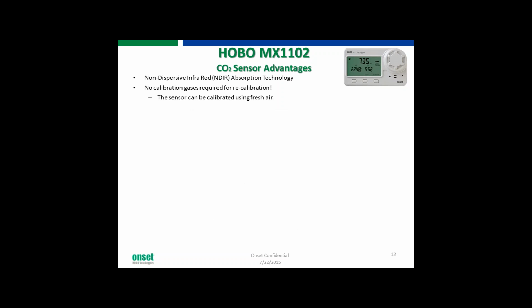I know one of the products that we still resell, the Telaire device from GE, I believe they use nitrogen, as you have to buy a calibration kit, where nitrogen represents 0 CO2. This product, you don't need to do that. You can calibrate it in fresh air, which, as we saw before, is between 350 and 450 ppm.